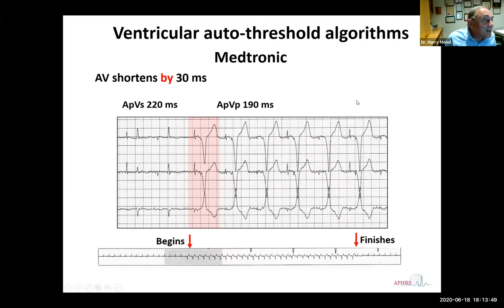Just to finish off with a Medtronic one, it only shortens by 30 milliseconds. So we have atrial pacing and ventricular sensing of 220 milliseconds. It shortens by 30 milliseconds, and now there is forced ventricular pacing. You can see on the bottom of the tracing how the algorithm progresses with reducing voltages until the threshold is determined, it finishes, and it goes back to atrial pacing, ventricular sensing at 220 milliseconds.